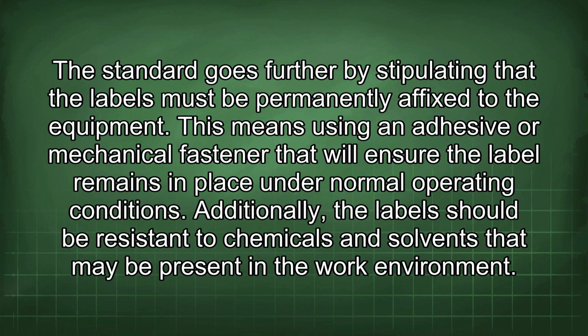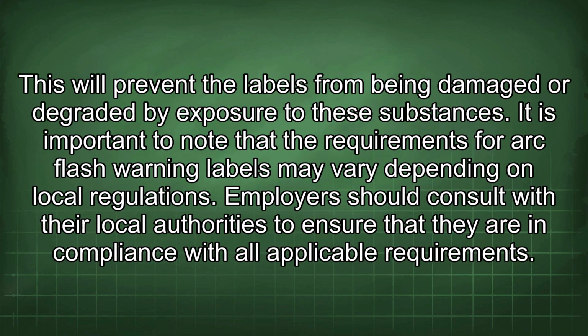The standard goes further by stipulating that the labels must be permanently affixed to the equipment. This means using an adhesive or mechanical fastener that will ensure the label remains in place under normal operating conditions. Additionally, the label should be resistant to chemicals and solvents that may be present in the work environment. This will prevent the labels from being damaged or degraded by exposure to these substances. It is important to note that the requirements for arc flash warning labels may vary depending on local regulations. Employers should consult with their local authorities to ensure that they are in compliance with all applicable requirements.